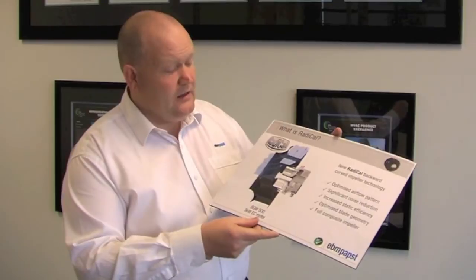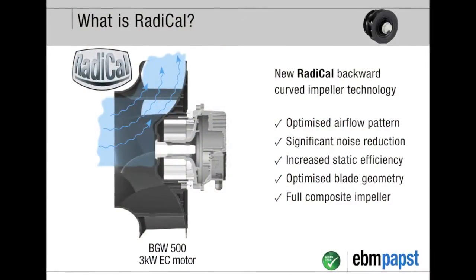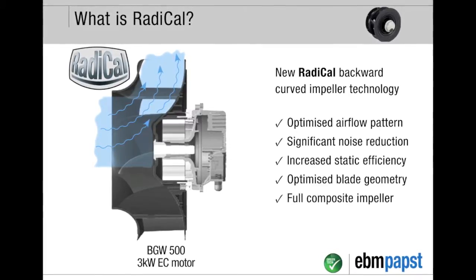Here is a cutaway section showing the design through the RadiCal impeller and how it's mounted on the EC motor. You can see the smooth airflow as it passes through the impeller. There is good power generation as we have three-dimensional blades inside the impeller, and we've also achieved static regain on the outside of the impeller to reduce air velocities. This is an optimized impeller giving high efficiency, which we then mount on our EC motor.